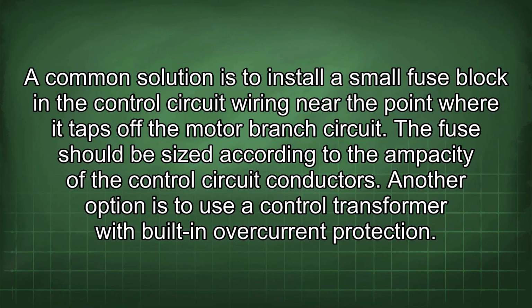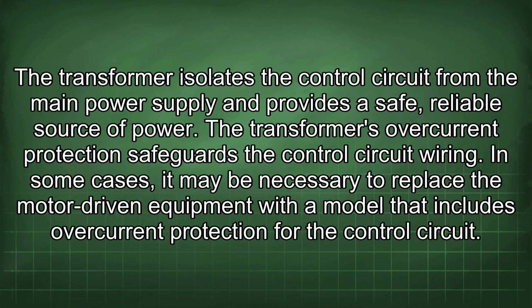Another option is to use a control transformer with built-in overcurrent protection. The transformer isolates the control circuit from the main power supply and provides a safe, reliable source of power. The transformer's overcurrent protection safeguards the control circuit wiring.